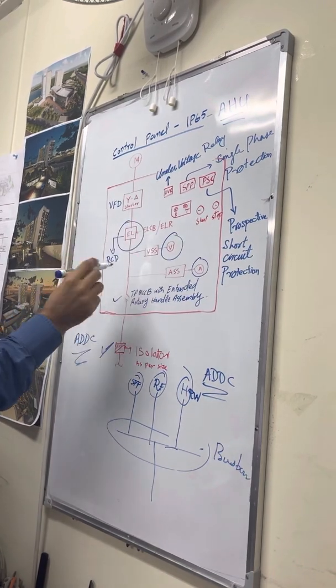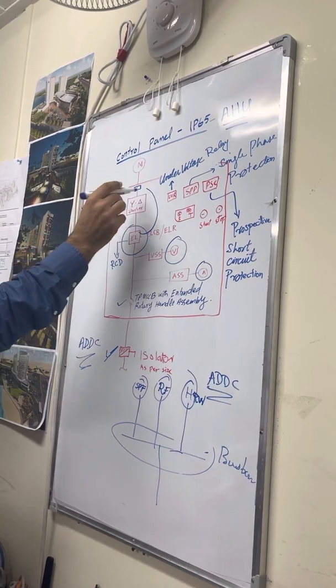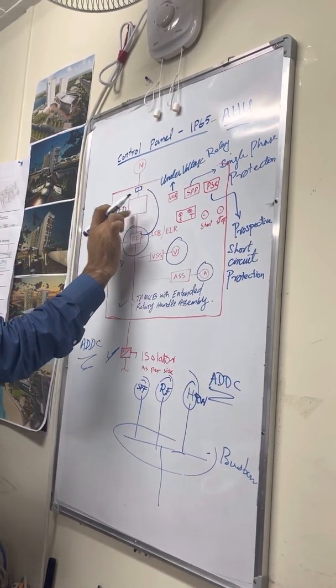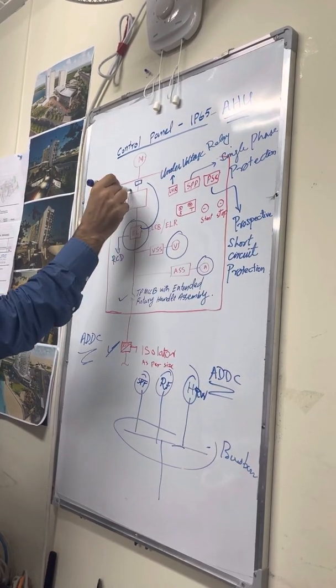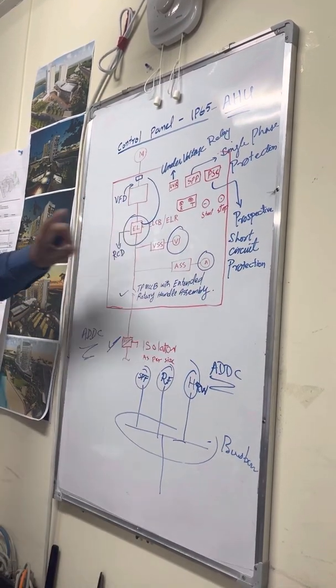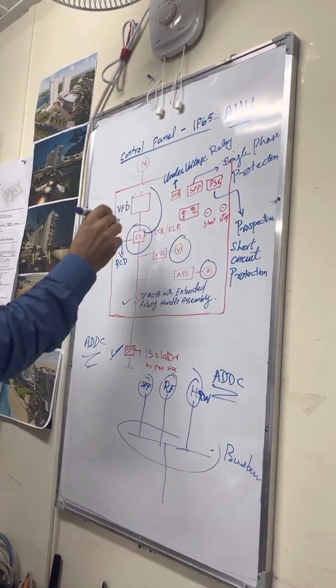And the important is the ELCB. Now this ELCB we cannot put here. It is not allowed to put after, for example if it is VFD. It is not allowed to put any earth leakage protection after the VFD. So it should be here. So this ELCB, it should be here.